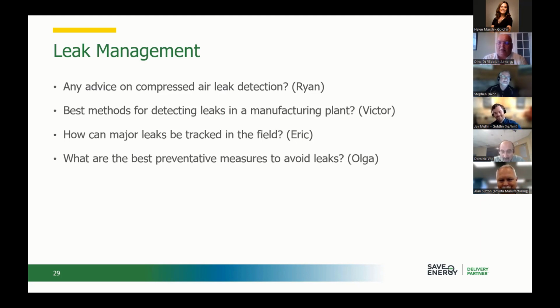Bandages don't work either. Yeah, it's interesting what you said about the flow meter, Dean. I was in a plant a while back that you'd been into before, and they were quite proud to show me that on their regular checks, three times a day, they check the airflow meter at the discharge of the compressor plant. They know what it's supposed to be, keep an eye on it, and respond when it creeps upwards. They also use the weekend loads to drive things downwards. At the end of the day, we can have all this technology, but simple procedures executed on a regular basis are really the key to the whole thing.